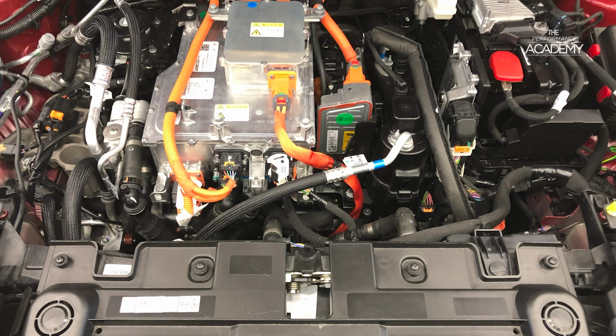Where there's no specific recommendation on test duration, we recommend using 1 minute, though for some tests on single circuits or components, the instructions will state for at least 10 seconds. You must not test for anything less than the time given. Always go over if not sure. The first installation test we will use as an example is the one we should all be familiar with, the complete electric vehicle high voltage driveline circuit test, which must be completed on every electric vehicle as part of the power-up procedure. For this, we will use one of our current BEVs.